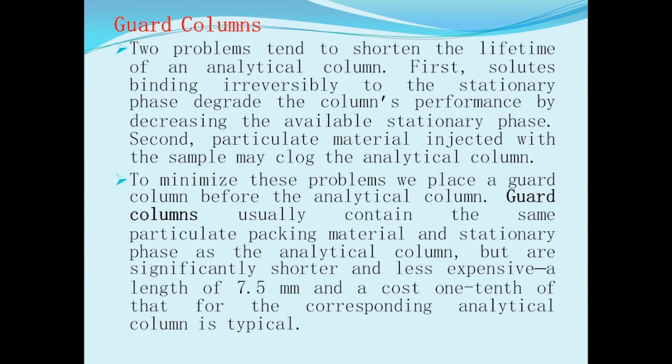Next, guard columns. Two problems tend to shorten the lifetime of an analytical column. First, solute binding irreversibly to the stationary phase degrades the column performance by decreasing the available stationary phase. Second, particulate material injected with the sample may clog the analytical column. To minimize this problem, we place a guard column before the analytical column.